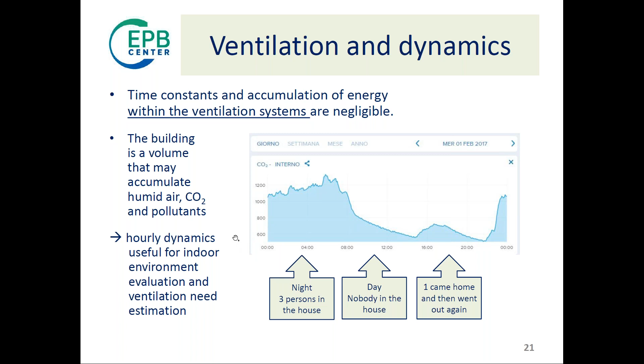And this is an example of ventilation and hourly. Please remember, hourly is not the same as dynamic. For example, air treatment requires a lot of energy, also for dehumidification in the Mediterranean climate. Conditions vary along the day and may be influenced by accumulation in the conditioned space. This was a concept from the previous slide. In the usual design routine, you calculate the air treatment in one design condition. The new EN standards are able to calculate air treatment for all hours. So you just describe the building and system only once.